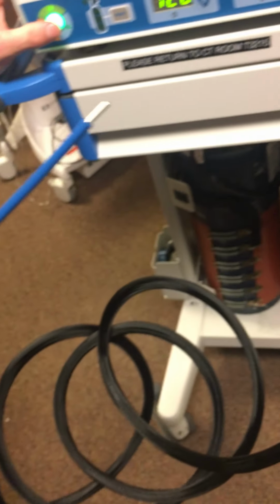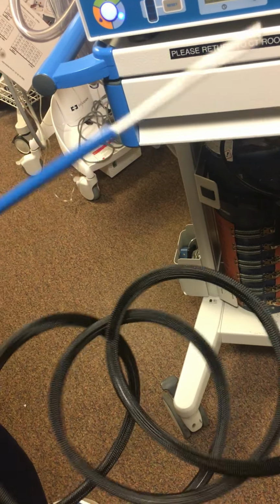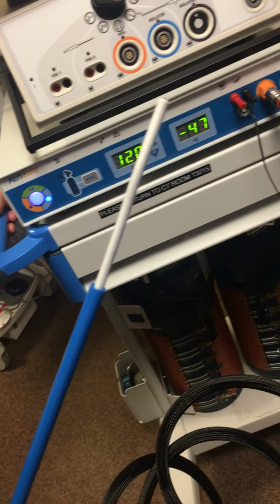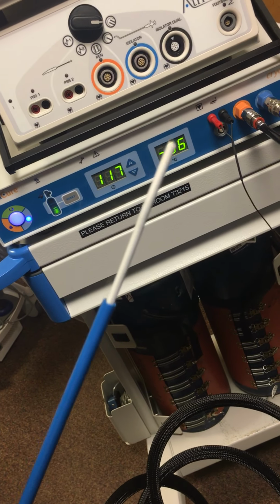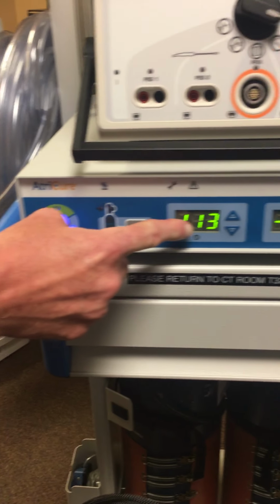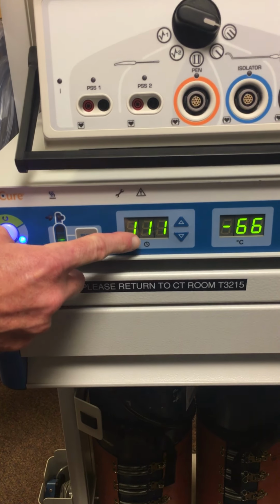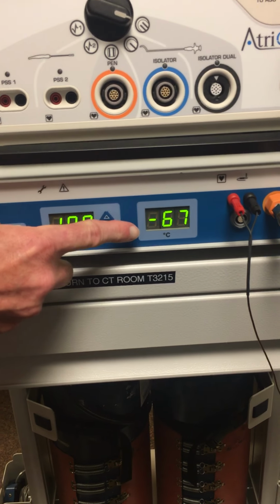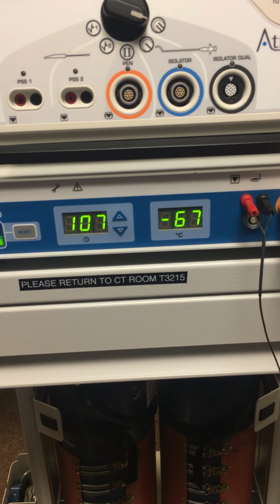We will go ahead and freeze at this point. Pressing the green button. We're also going to show you the Cryo Probe too, to see that we know it's freezing. If we come back to the generator, our light is blue, meaning that it's freezing. Timer's already been started. We're at 110 seconds now, and we're at negative 66 degrees Celsius.